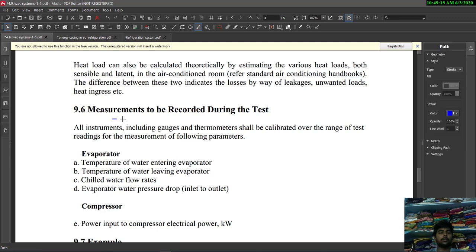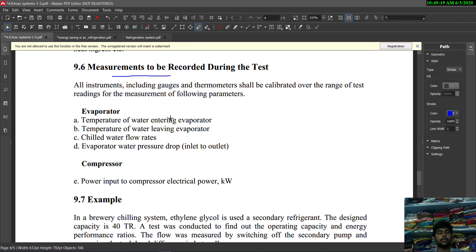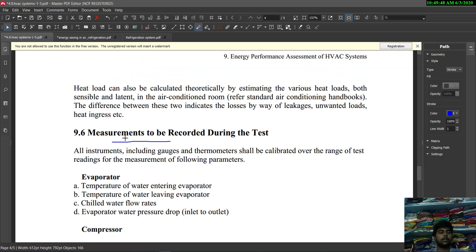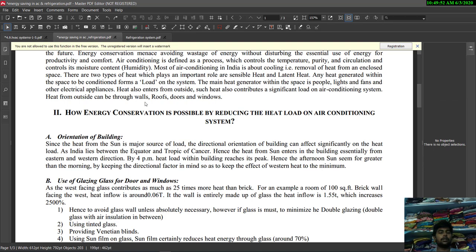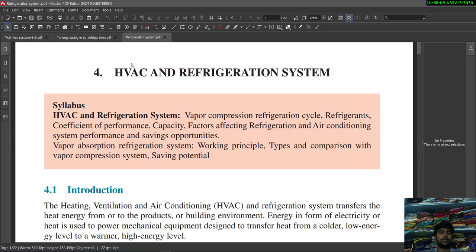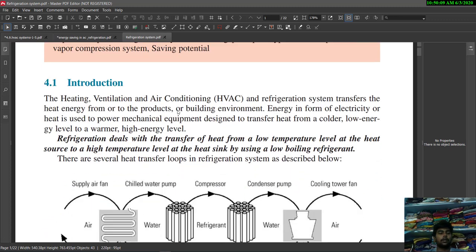The measurements to be recorded during the test include: in the evaporator — temperature of water entering and leaving the evaporator, chilled water flow rates, and evaporator water pressure drop; and in the compressor — power input to the compressor in kilowatt. Refrigeration is defined as the transfer of heat from a low temperature level at the heat source to a high temperature level at the heat sink using a low boiling refrigerant.